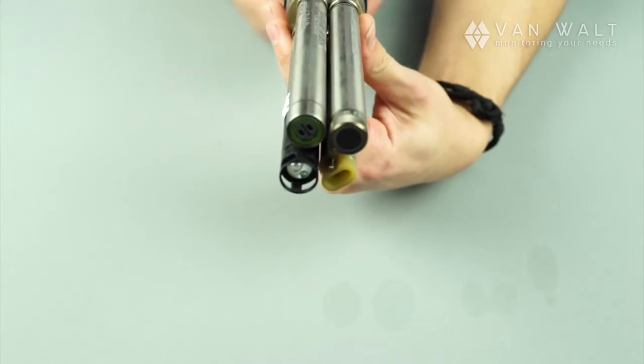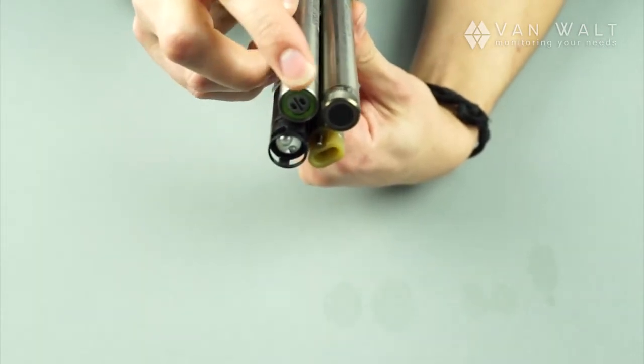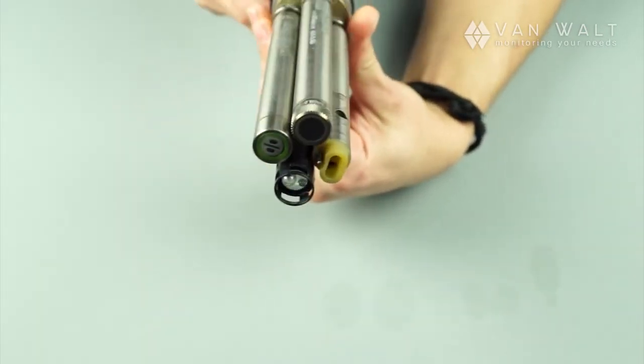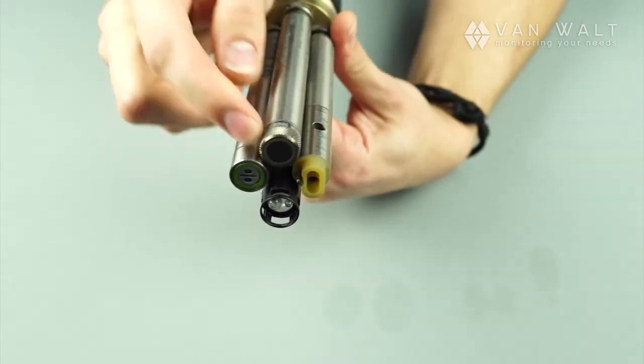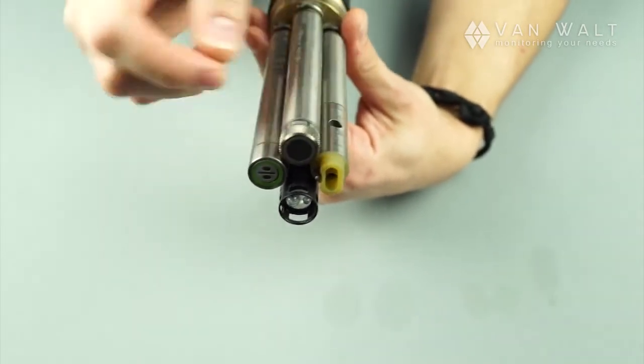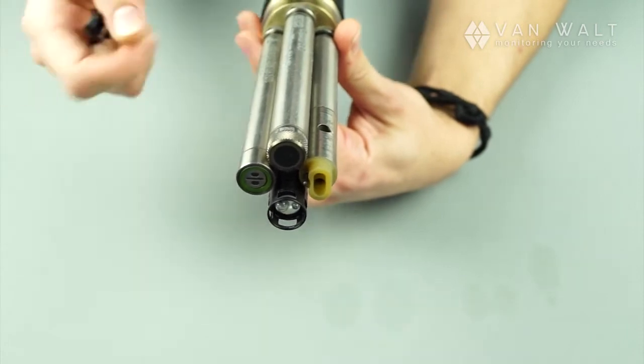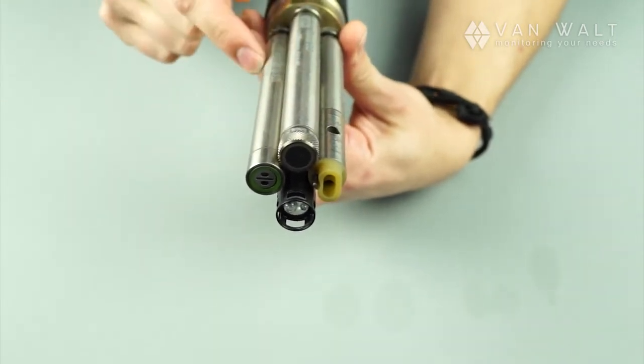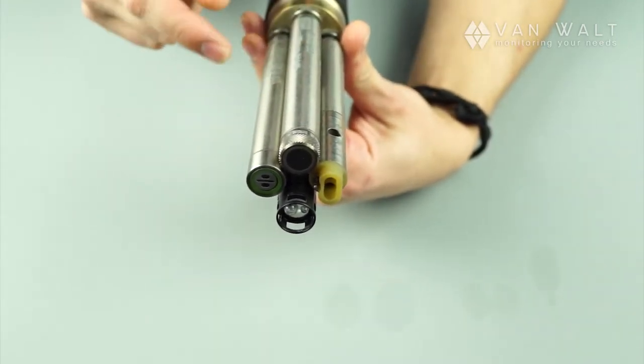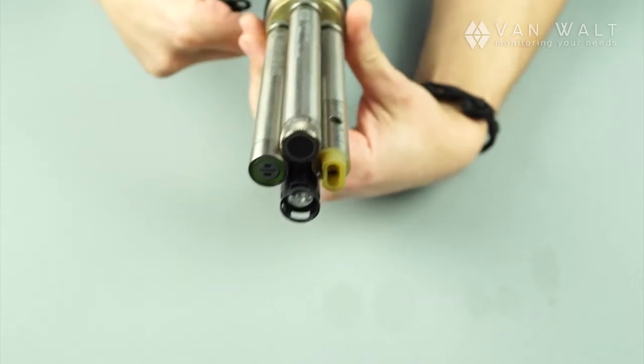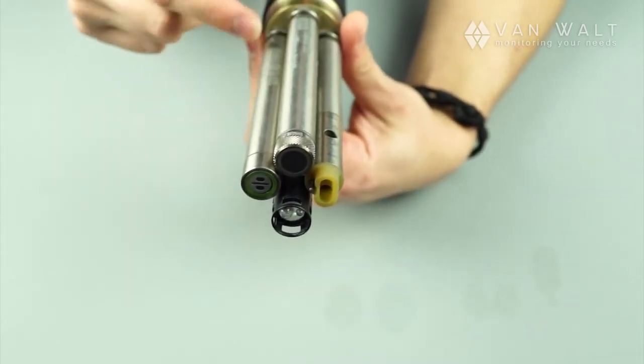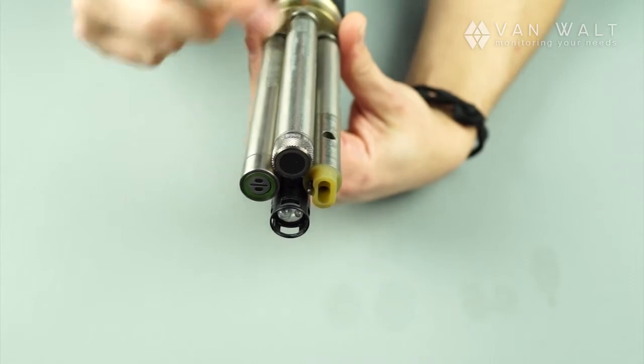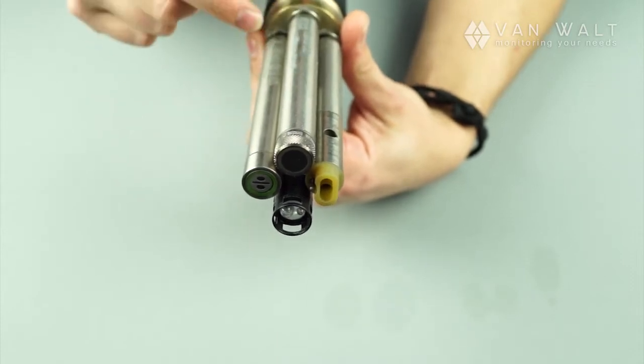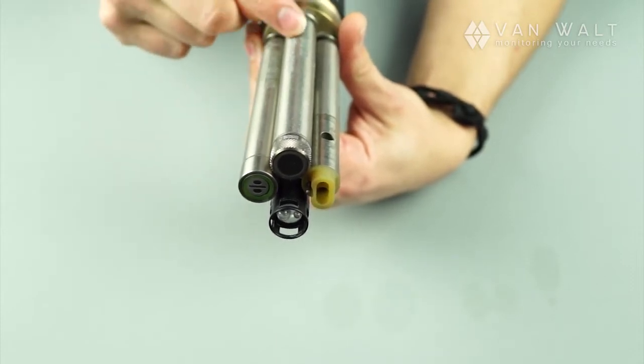You can see here in our turbidity probe the 2 lasers there. Optical DO has a cap on it. This lasts approximately 1 year. Each of these probes can be swapped around. There's no specific place for them to live, so if you're calibrating your unit, you can calibrate multiple probes on one unit and return them to any socket, and the device will automatically register what's in the correct port.